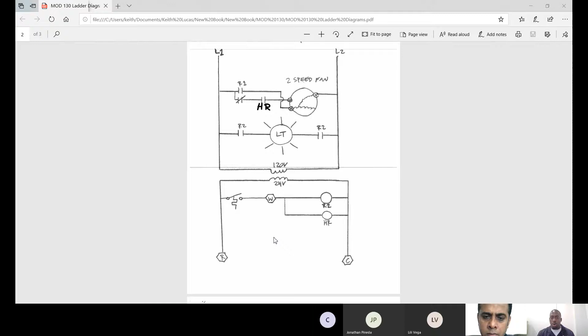Just a quick recap. We know these are contactor contacts. We know this is our relay, and that's our temperature switch, cooling terminal, fan or cooling circuit, fan circuit, contactor coil, relay 1 coil. Up here is all 120 volt stuff. All these components down here operate on 24 volts. And this is our transformer in the middle. The transformer is connected directly to our L1 and our neutral, and all that 120 volt power comes in through the primary side of the transformer, then it's stepped down to 24 volts on the secondary side, and that's what operates our contacts. Whenever we energize or de-energize the coil, that closes or opens our contacts and allows us to either operate or not operate all these components up here.